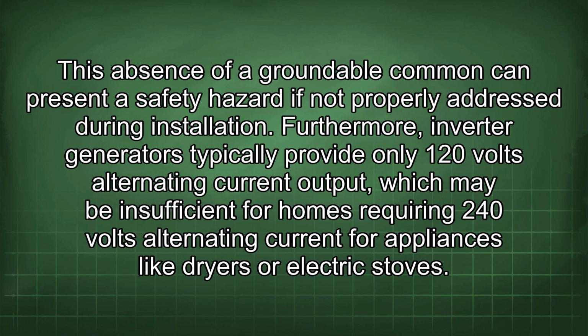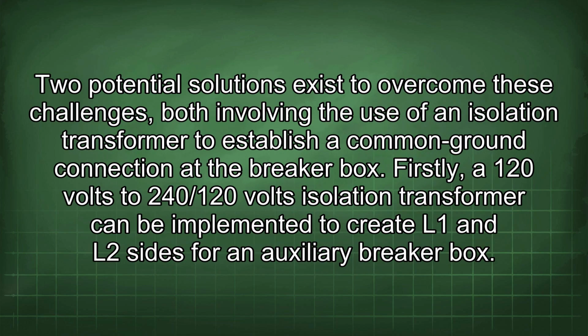Furthermore, inverter generators typically provide only 120 volts alternating current output, which may be insufficient for homes requiring 240 volts alternating current for appliances like dryers or electric stoves. Two potential solutions exist to overcome these challenges, both involving the use of an isolation transformer to establish a common ground connection at the breaker box.